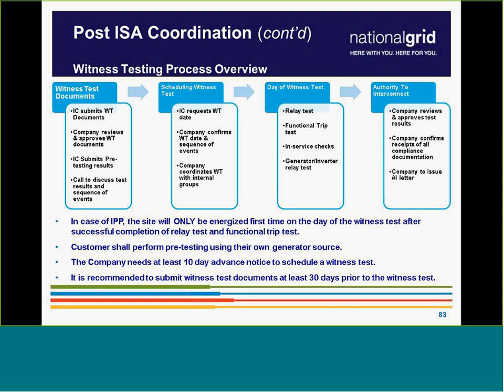On the day of the witness test we do relay testing, functional trip test, in-service checks, generator, inverter, relay test. Sometimes that can be done in one day, sometimes two. I always book a rain date with my witness test date in case there's weather issues or equipment problems, so there's time to fix it or try again. If the project has only one relay it might be a couple hours of work, but there are always issues you never accounted for, which is why I schedule that rain date.